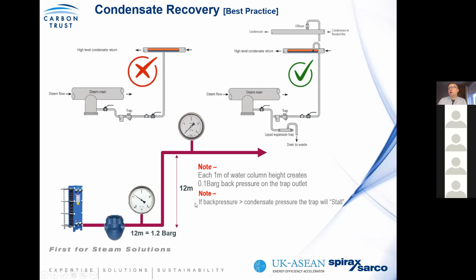Now, what's important to understand is that where you have a water column height, if this back pressure is greater than the pressure that's within the heat exchanger, the system will stall. What you need to understand is, according to the steam tables, pressure is proportional to temperature. And when you're controlling to a temperature, especially anything less than 100 degrees, it is very common to have atmospheric or sub-atmospheric pressures within the heat exchanger here, even if you have steam pressure available to the control valve. So where the pressure is less than the back pressure, the trap cannot remove the condensate effectively, and you'll experience temperature swings, poor control, or lack of controllability.